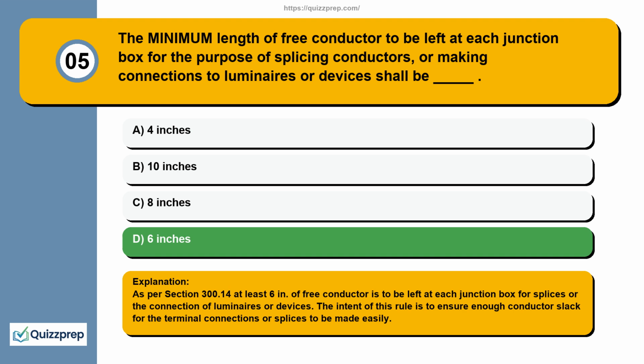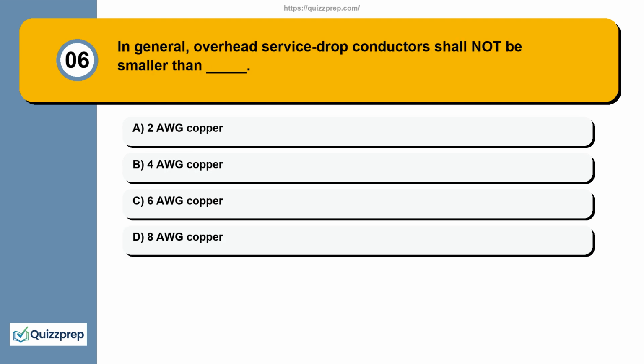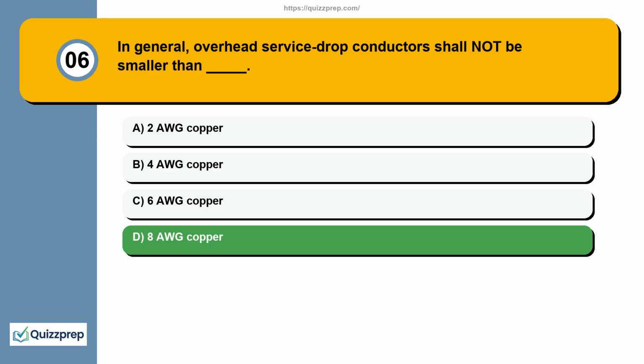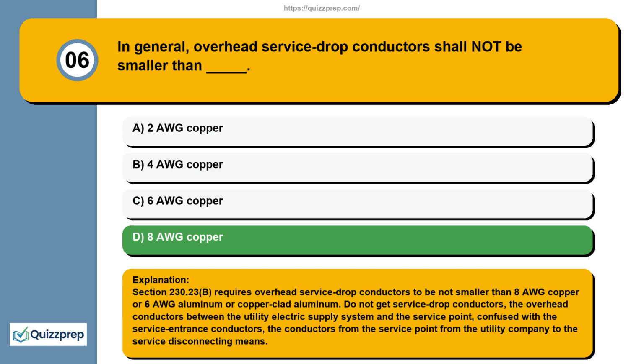Question 6. In general, overhead service drop conductors shall not be smaller than 2 AWG copper, 4 AWG copper, 6 AWG copper, 8 AWG copper. Section 230.23(B) requires overhead service drop conductors to be not smaller than 8 AWG copper or 6 AWG aluminum or copper-clad aluminum. Do not get service drop conductors, the overhead conductors between the utility electric supply system and the service point, confused with the service entrance conductors, the conductors from the service point from the utility company to the service disconnecting means.